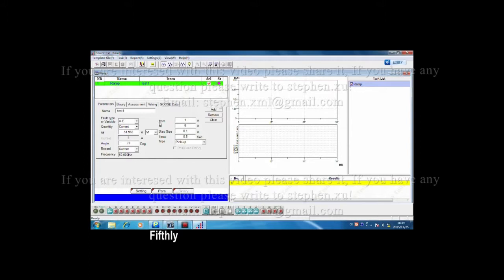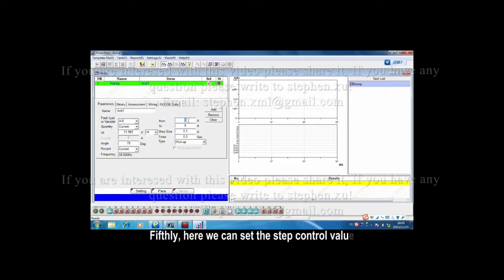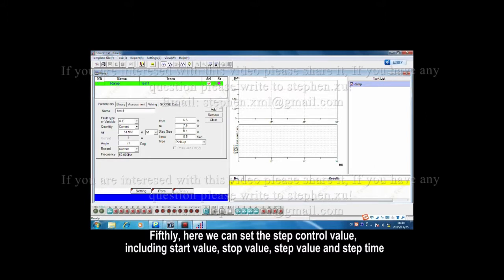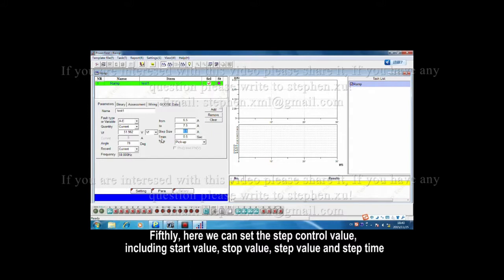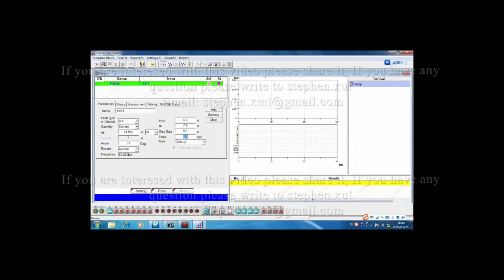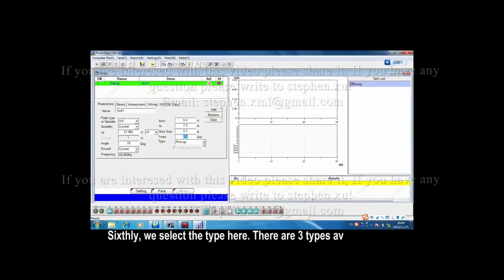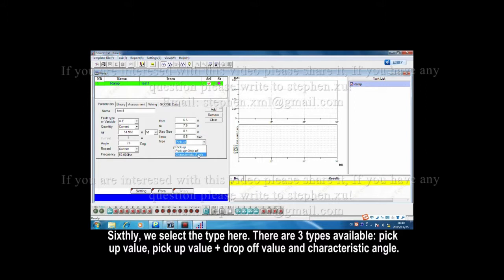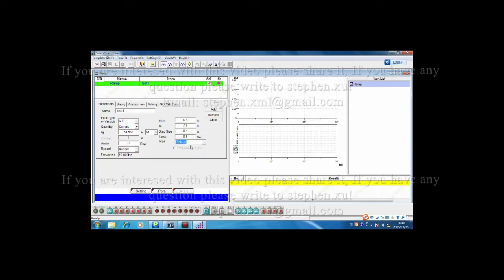Here, we can set the step control value, including start value, step value, stop value, and step time. We select the type here. There are three types available: pickup value, pickup value plus drop-off value, and the characteristic angle. We choose pickup value here.